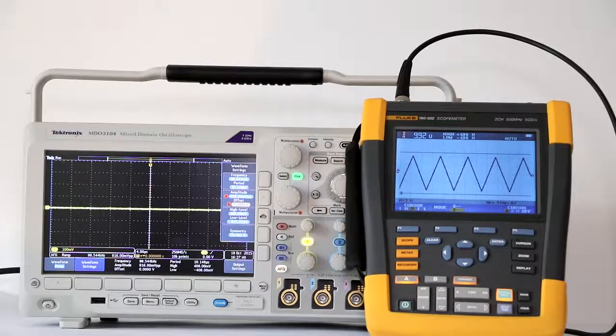The great value of the cursor mode is that the metrics shown in the cursor readout are far more accurate than you could expect by counting divisions and ticks on the screen. To explore more of the cursor features, first make sure that the cursor menu is on the screen by pressing the cursor button. With the cursor menu in place, the F4 button scrolls through the menu items.